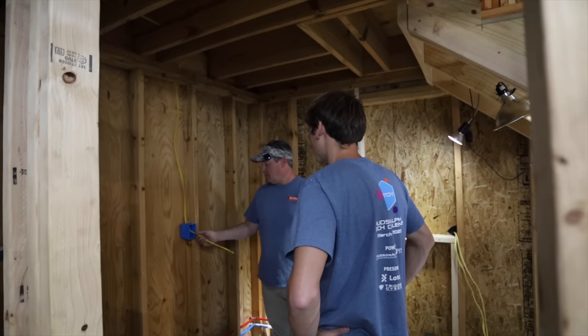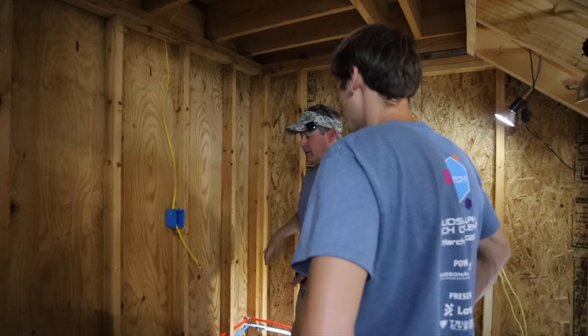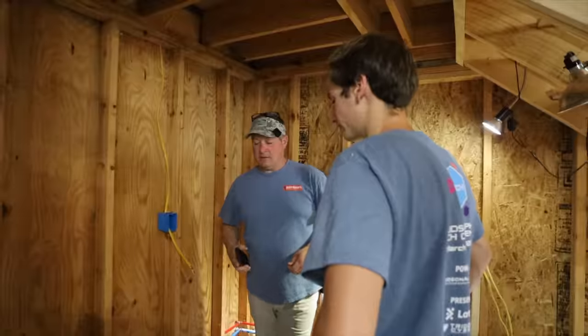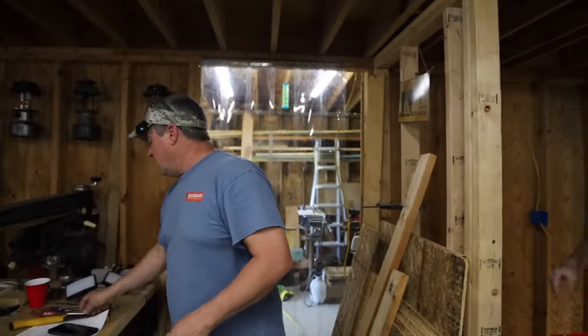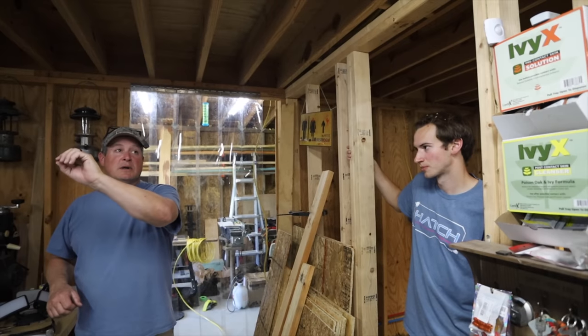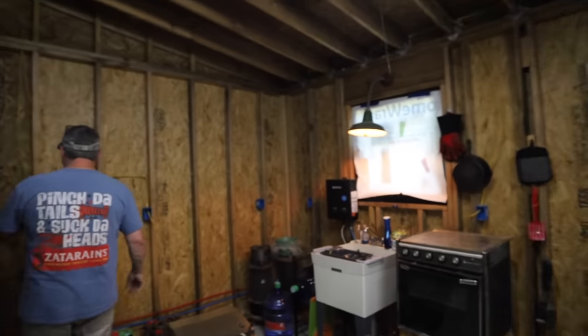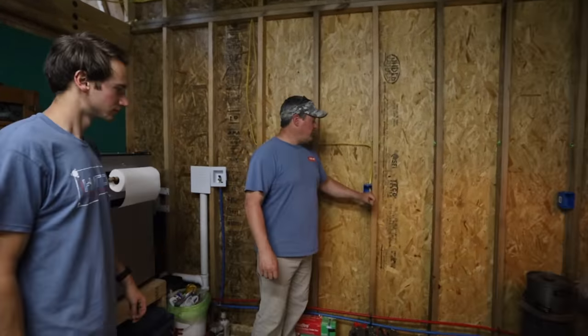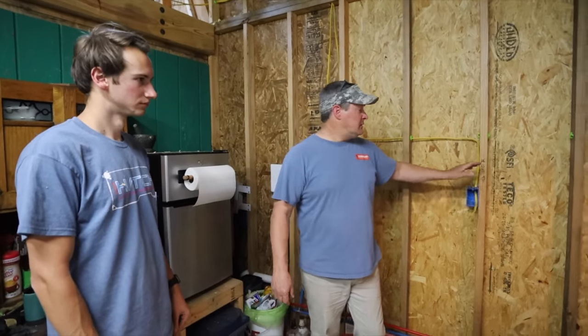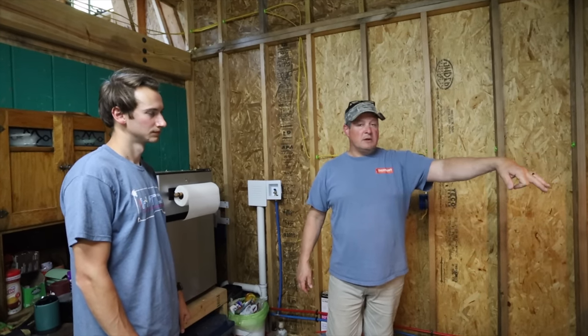Everything past this point is going to be GFCI protected because you're going to have either a GFCI outlet in here or a GFCI outlet in the panel, one of the two. But whatever we do, even though we need outlets outside in some places, we can't go out of this room since we're running one circuit anywhere else. So 20 amp comes in and only stays in the bathroom — can't jump anywhere else. We've pulled several to the kitchen and still have some more to go, and we've still got home runs to pull upstairs. All we've pulled so far is the refrigerator dedicated circuit and we're going to pick up our GFCI circuit for the required two 20-amp small appliance countertop circuits.